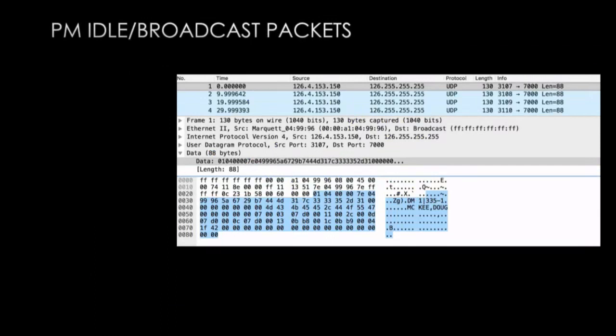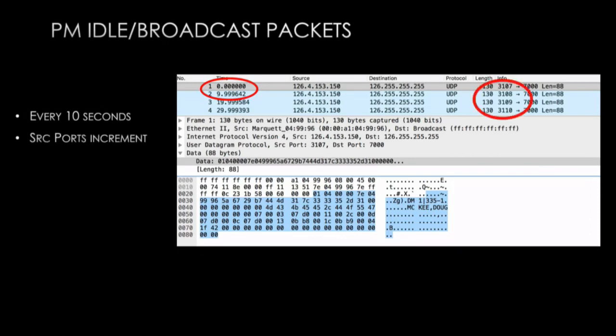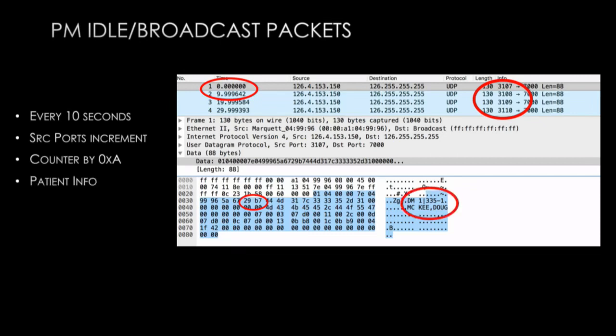Next, I powered off the central monitoring system and powered on only the patient monitor. Once again we saw broadcast packets going across the network. Every 10 seconds approximately a packet is sent. The destination port is the same, however the source port increments by one every single time a packet is broadcast. Staring at hex long enough, at offset approximately 34 there is a counter being incremented by 10 each time — not coincidentally, the same as the number of seconds between packets. And you can see clearly in plain text that patient data is going across the network. These are broadcast packets — not going directly to a single device. Combining a patient's name, room number, and bed number, as Dr. Nordic noted, constitutes HIPAA data.